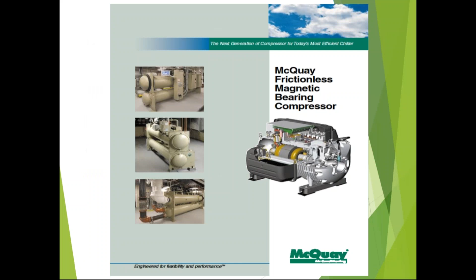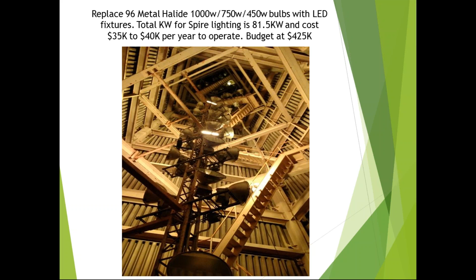This coming year is a lighting project. There's a spire, and we're going to put in LEDs, upgrading these old metal halide lights—1,000 watt, 750 watt, and 400 to 450 watt bulbs. It's about 82 kW per hour to run them. They only run 4 to 6 hours depending on daylight savings, and it costs $35,000 to $40,000 a year to operate. But to replace them with LEDs would cost $425,000. Even with energy savings, the payback is way out there, so it's more of an infrastructure-type project. That covers our projects for 2016.